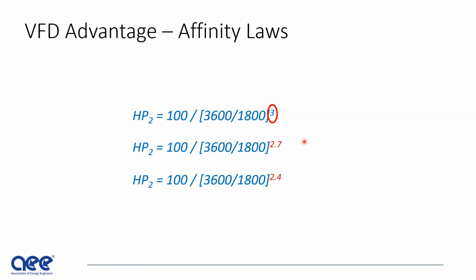The other thing with the affinity laws is, notice we kept the exponent at 3. In reality, it's never 3. A rule of thumb is 2.7 to be conservative. With fans, I would use 2.7. It could also be lower than 2.7. And if you're filing for a rebate with a VFD on a motor, the utility is going to take a close look at this because it's not just the efficiency of the motor, but what is attached to that shaft.